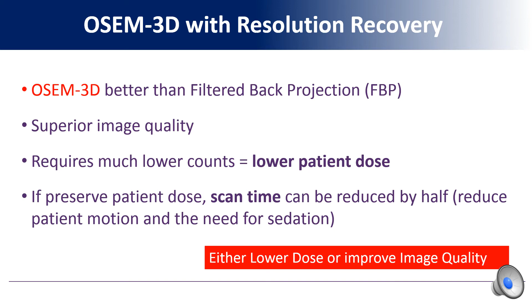OSEM 3D definitely does better than the filtered back projection. It provides superior image quality and requires much lower count. That means we can reduce the patient dose, or if we want to preserve the patient dose, we can reduce the scan time. When we reduce the scan time, it is possible to reduce patient motion, so we can achieve a better image quality and reduce the need for sedation. So we can choose either to lower the patient dose or improve the image quality.